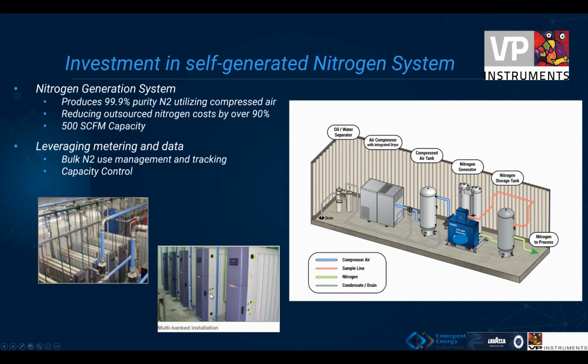The compressed air demand from this facility is about 2,500 CFM, which translates to roughly 500 to 600 CFM of nitrogen. Metering on the nitrogen system helps determine system capacity constraints and generator efficiency. It also gives a pulse of how production is running based on nitrogen flow. The facility uses nitrogen to purge its fillers, so the more nitrogen used, the more downtime they're experiencing. The site actively manages its bulk nitrogen use through the VP meters.